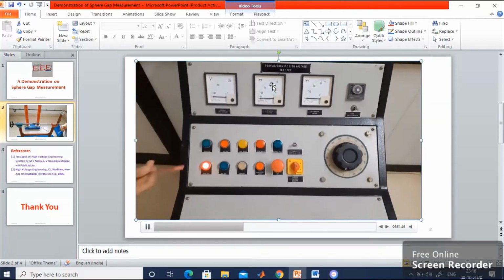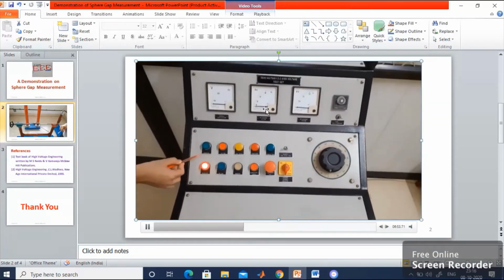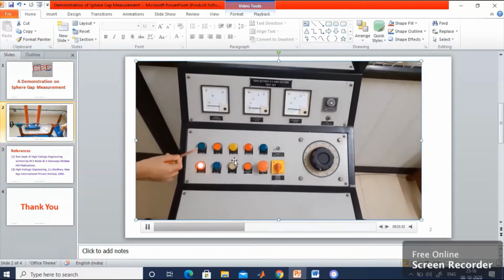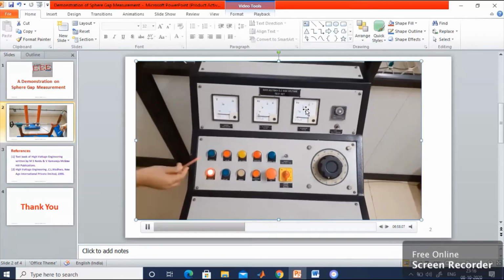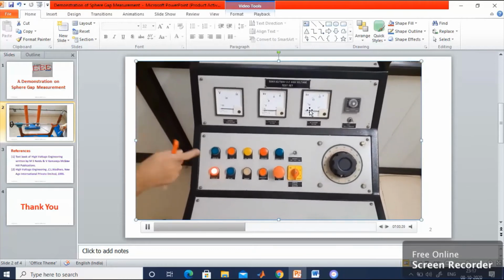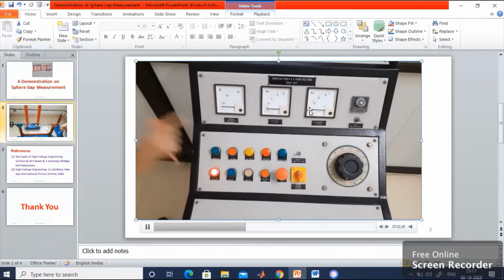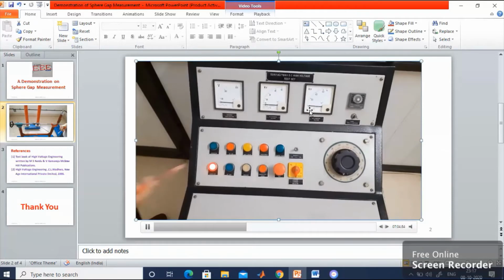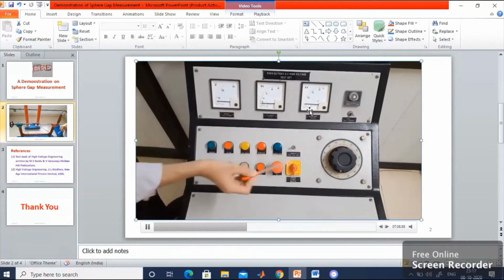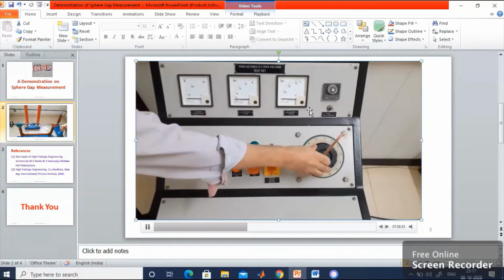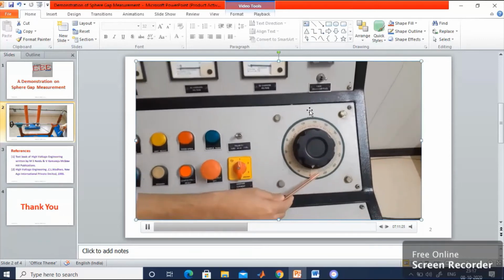One more important piece of information: for HVAC we have a memory option, you can see the memory. For HVDC we don't have any memory option, so immediately you have to note down when the dielectric breakdown voltage occurs, when the breakdown happens. You should have keen observation, especially while doing HVDC. For measurement of HVAC it doesn't matter since you have the memory button.